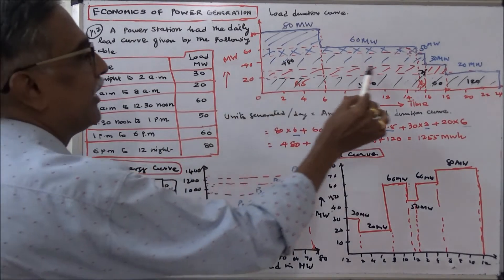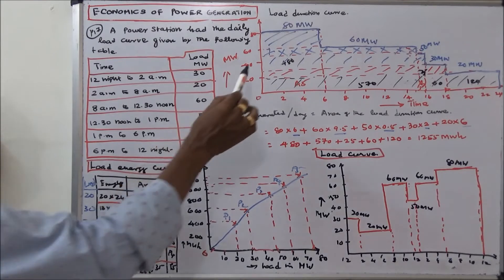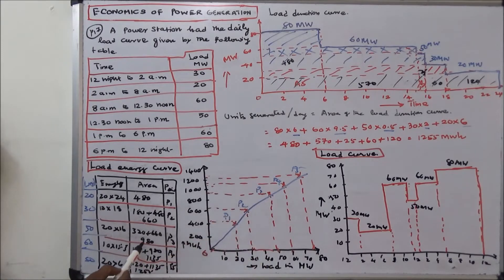For area A3: 20×16 = 320; 320 + 660 = 980 — point P3 at 50 MW. For area A4: 10×15.5 = 155; 155 + 980 = 1135 — point P4 at 60 MW. Last, area A5: 20×6 = 120; 120 + 1135 = 1255 — point P5 at 80 MW. This curve is called the load energy curve.